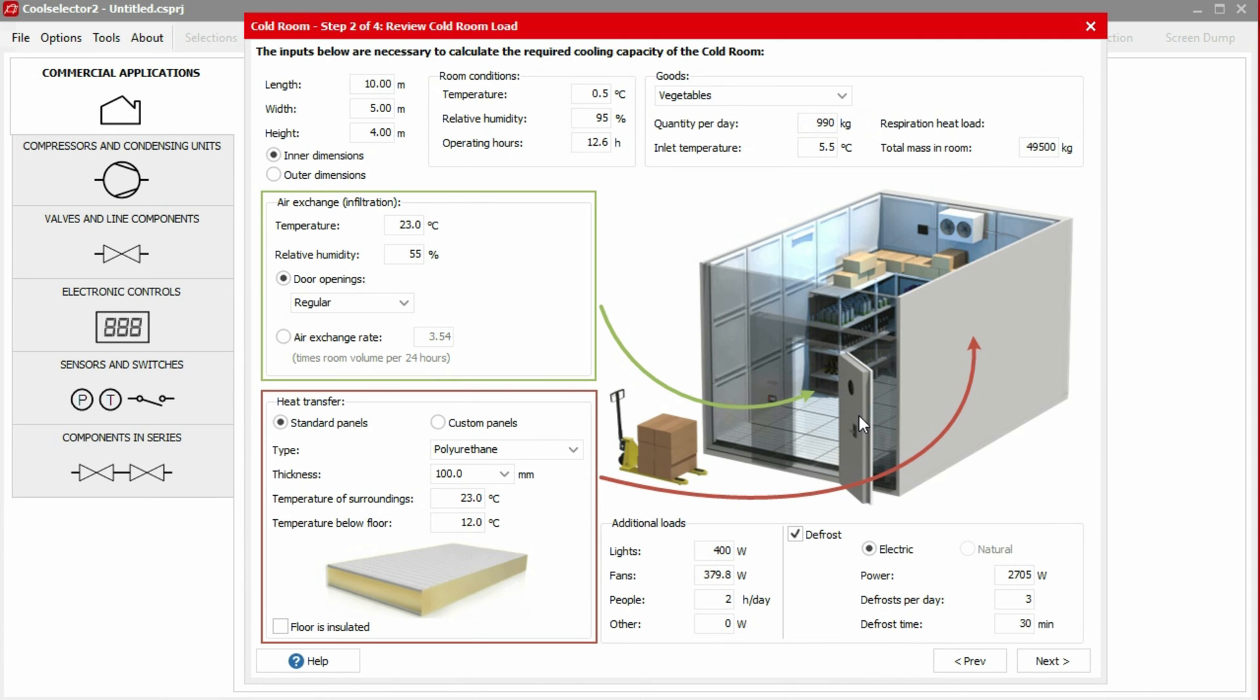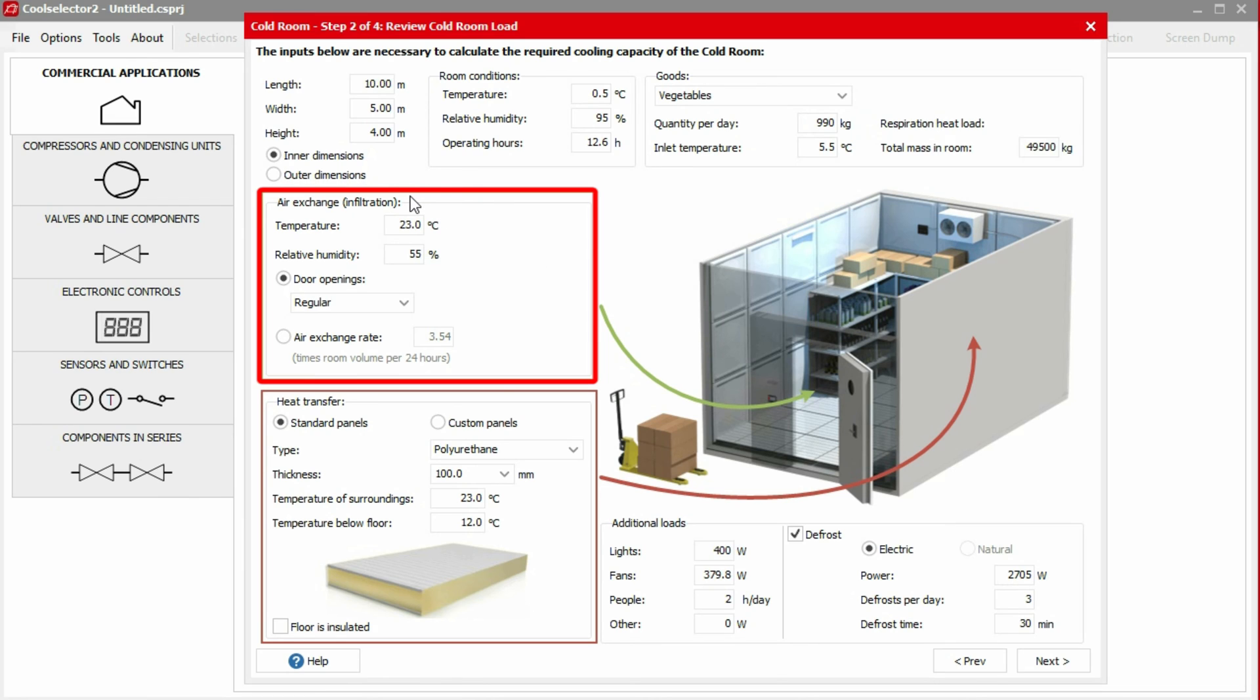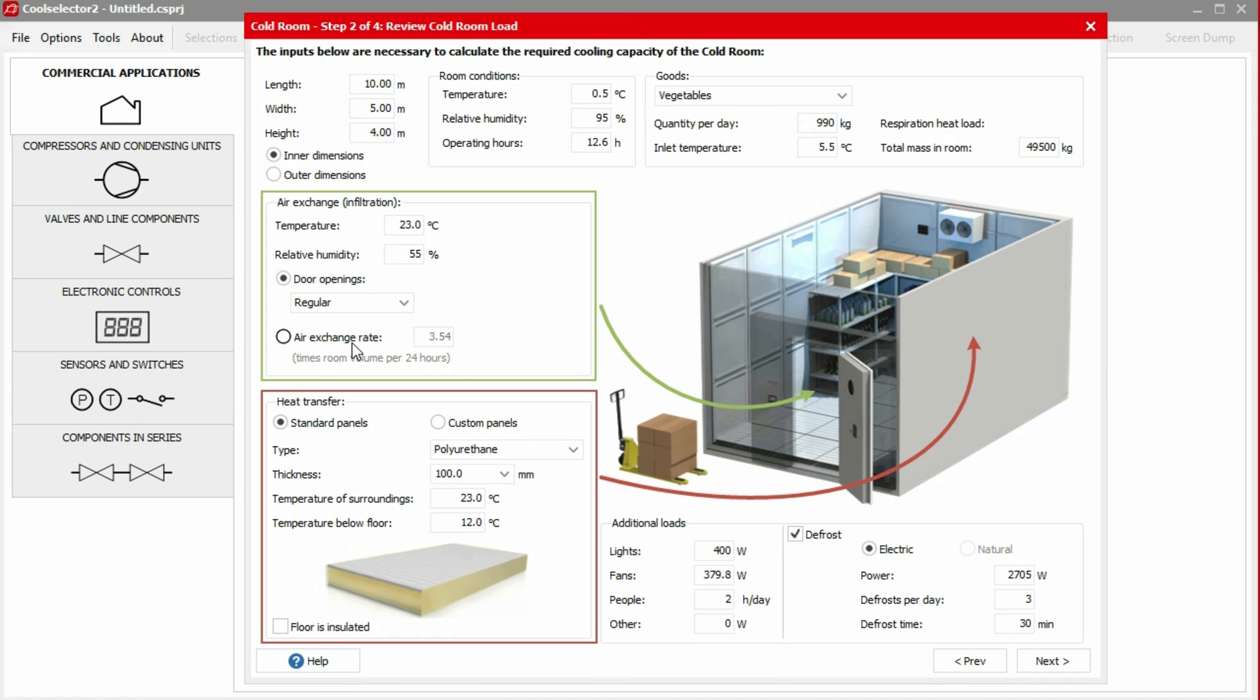The window will now refresh and display an overview of our cold room. The values impacting the heat load are displayed here and can be adjusted if needed. We also have some additional inputs, which are not included in the wizard. We need to specify the air exchange from the room as the infiltration will impact the cooling load. We can choose the door openings where the wizard estimates the infiltration, or we can manually specify the air exchange rate every 24 hours.